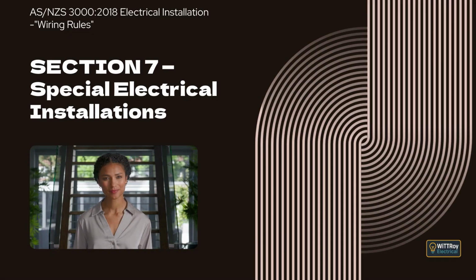This clause explains that live parts of SELV circuits must not be connected to earth, protective earthing conductors, exposed conductive parts of other systems, or extraneous conductive parts. It explains limited exceptions where connection to extraneous conductive parts is inherently required and voltage cannot exceed SELV limits. It also explains that where SELV circuits may come into contact with other exposed conductive parts, protection against electric shock may depend on the protection applied to those other parts. It explains that where nominal voltage exceeds specified values, basic protection must be provided by barriers, enclosures, or insulation capable of withstanding specified test voltages.